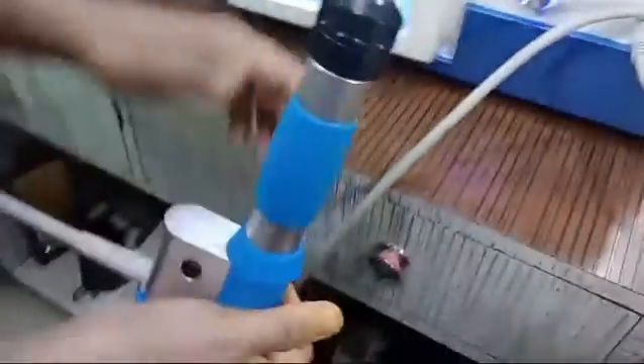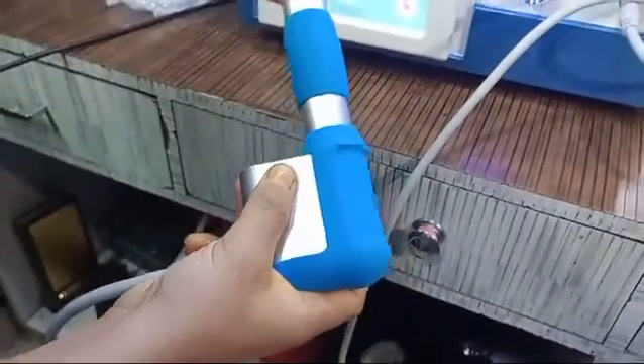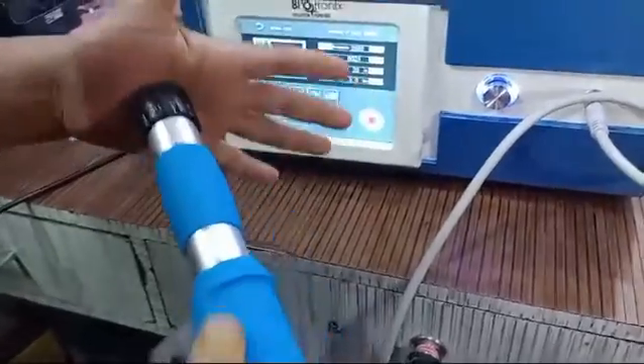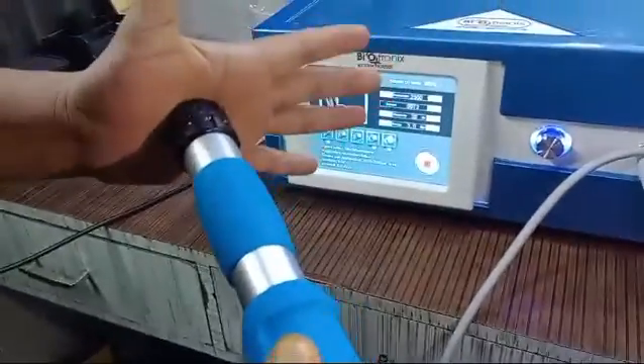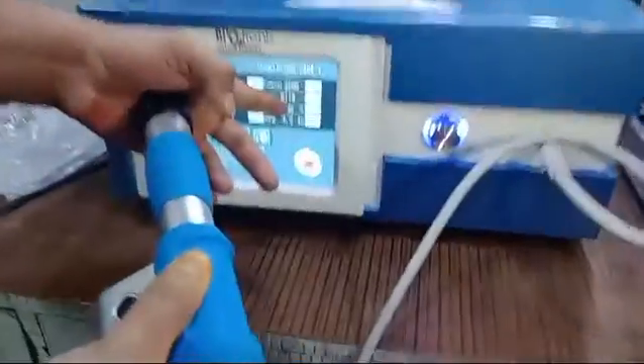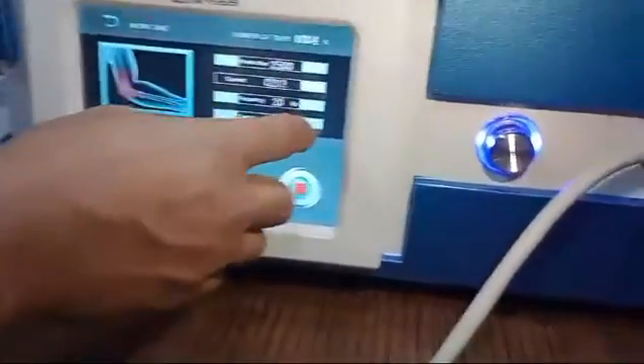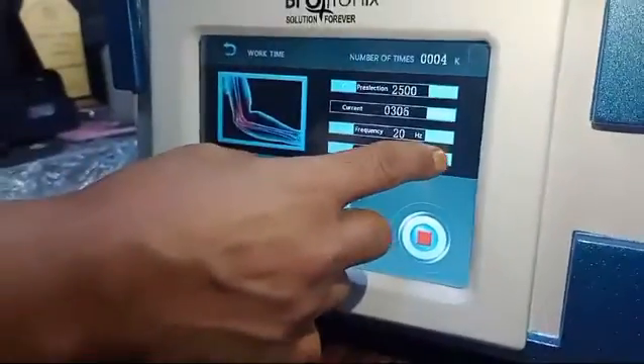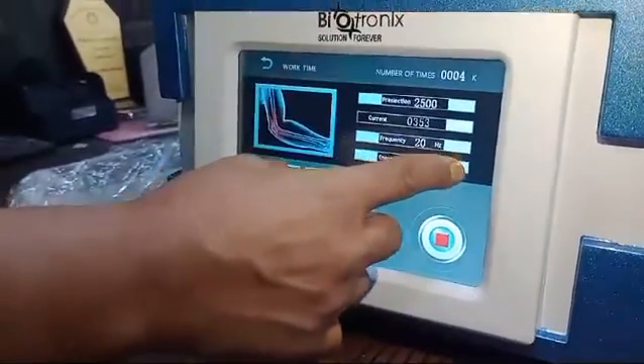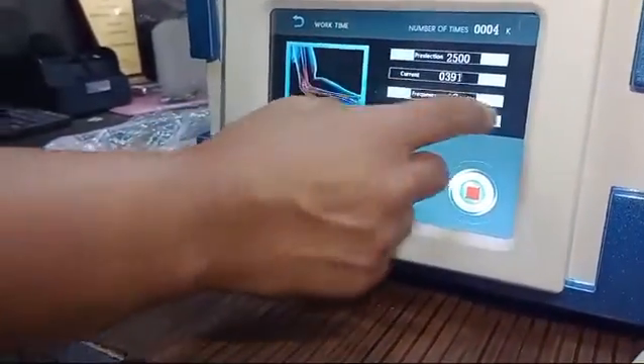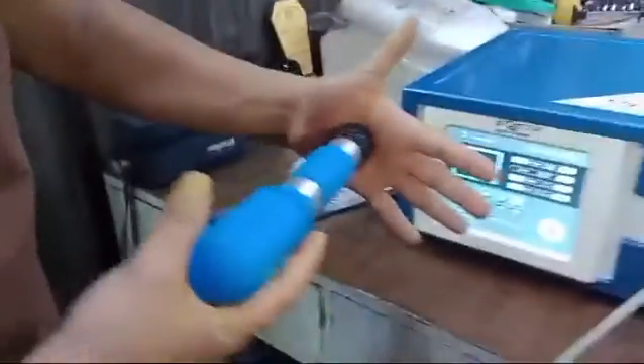I have connected the probe like this, and this is the probe. Now press the start button. You can see the start button has been pressed, and this is the operation button in the probe. Like I have to press the same. You can see I'm getting this. You can see the number of shots coming, and if I increase the energy to, I'm decreasing the frequency. You see decreasing the frequency.